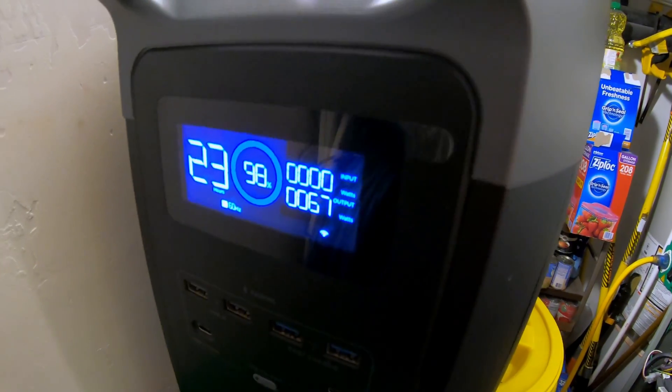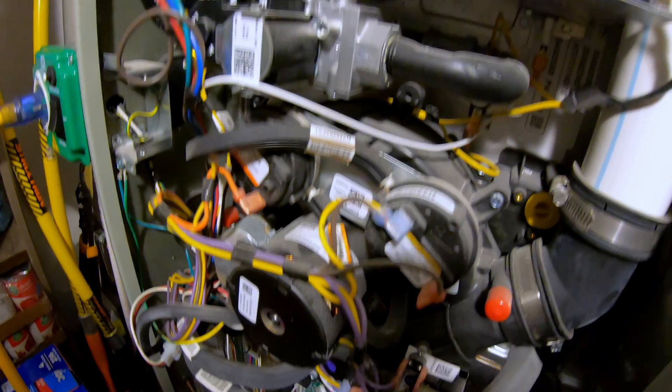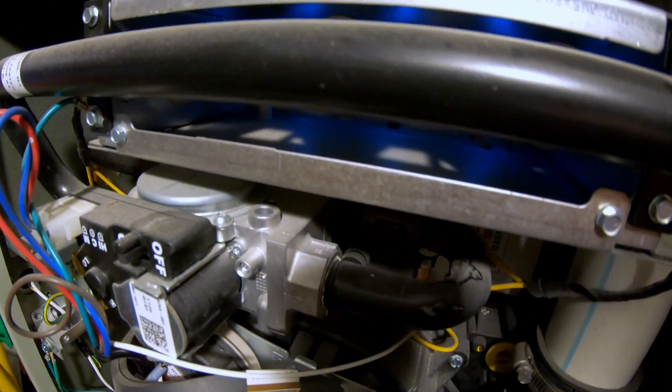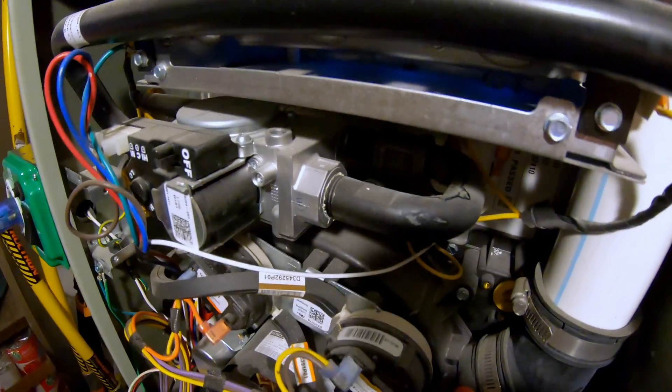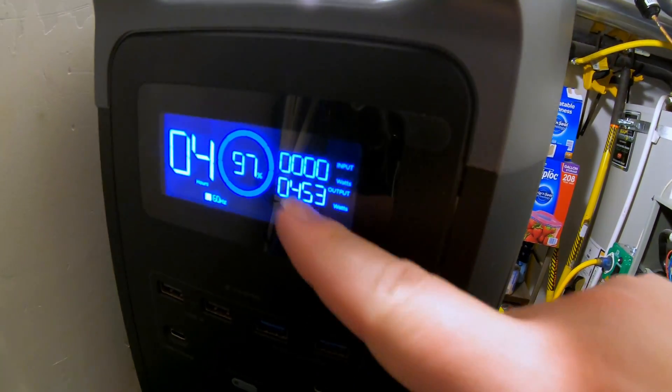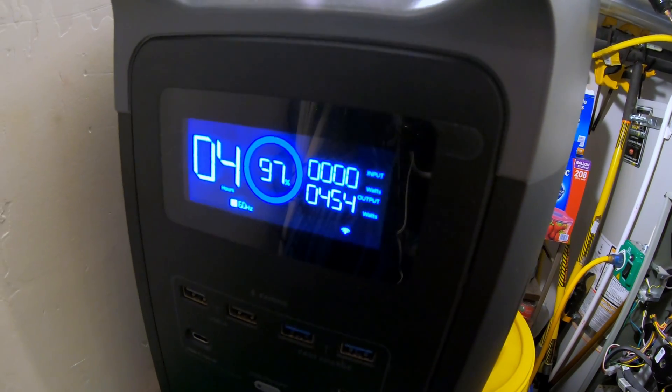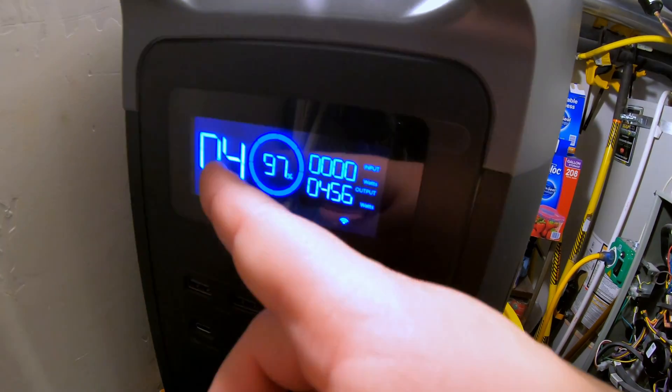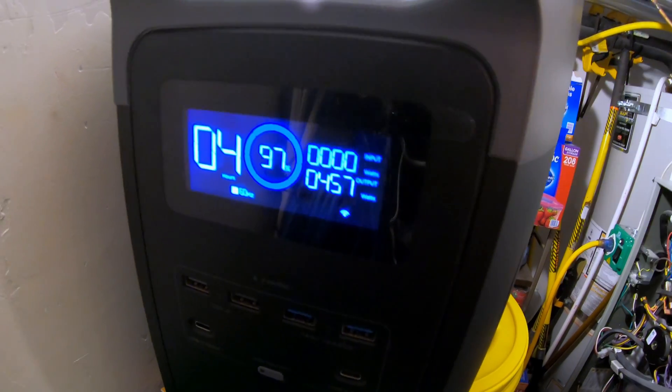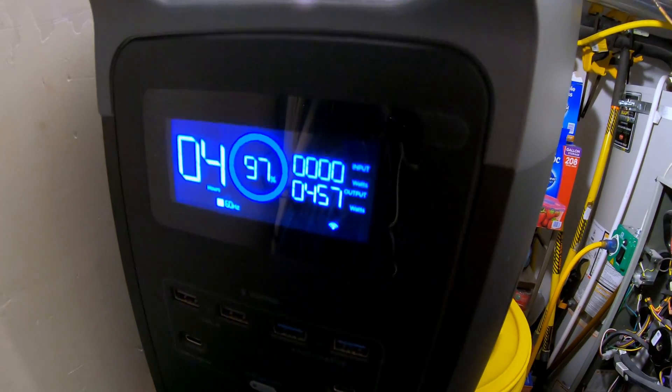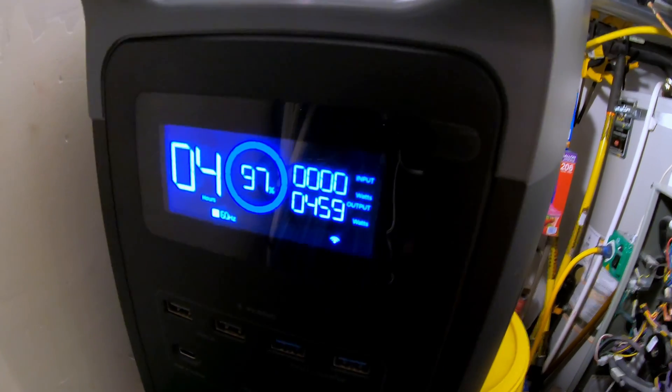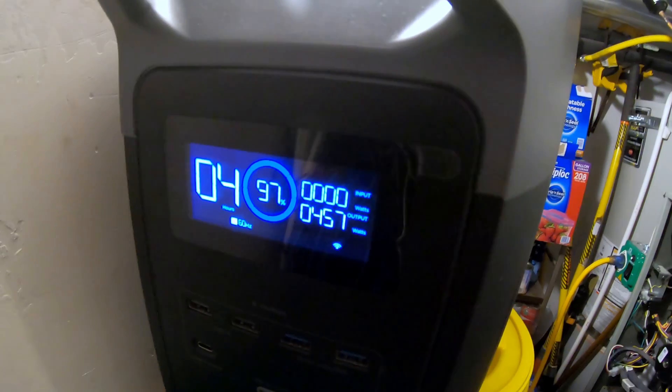Let's see what happens when the blower comes on. Okay, I don't know if you can hear, but the fan is now up to speed. Let's check it out. So just over 450 watts. So this is estimating 4 hours. Actually, if you do the math, if this is at 100% state of charge, you probably get just over 4 hours run time for the furnace.